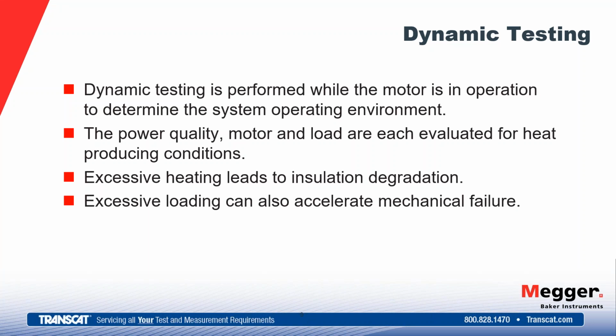So these things that it can identify are things that lead to excessive heating and insulation degradation. We can see issues with power quality that actually lead to heating in the motor. And if they're present, then we're degrading that motor much faster than we would if we were giving it good power.